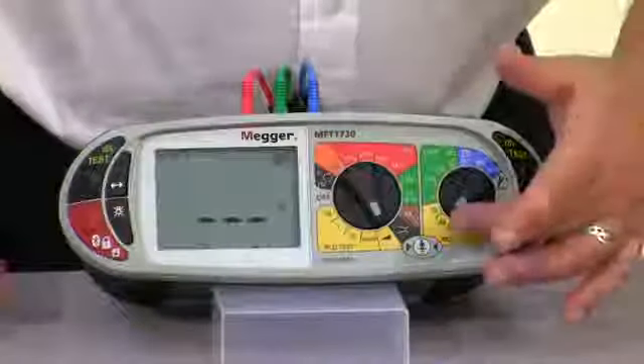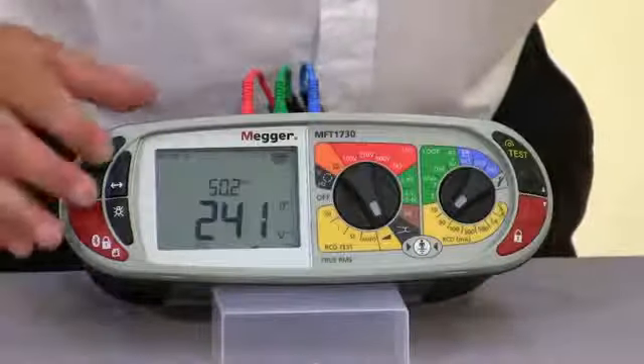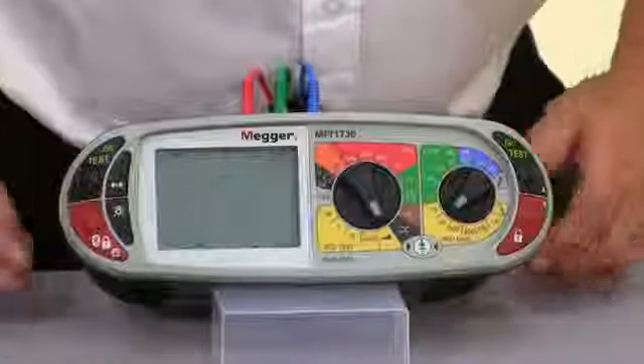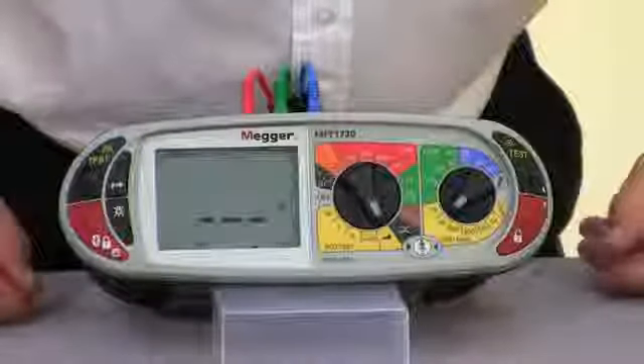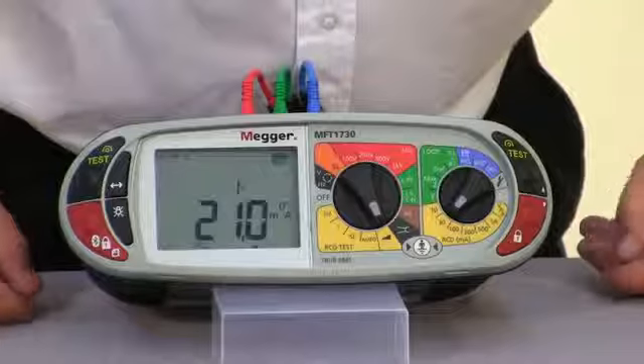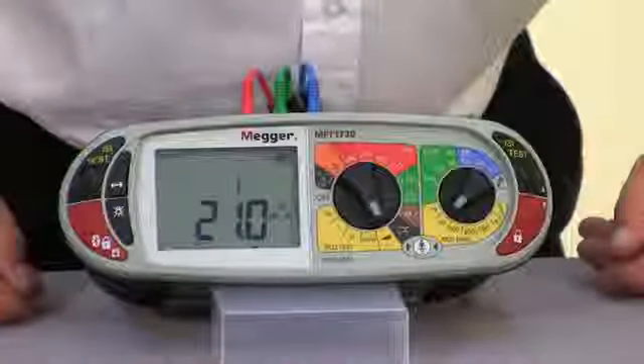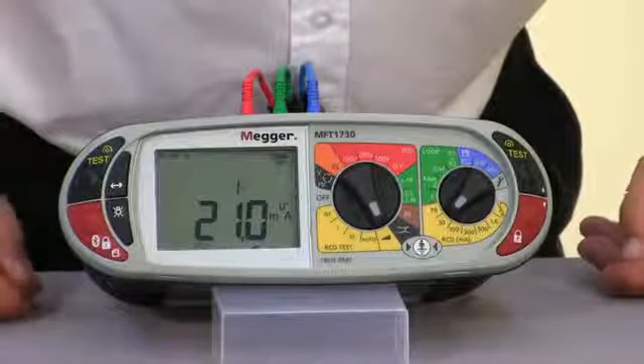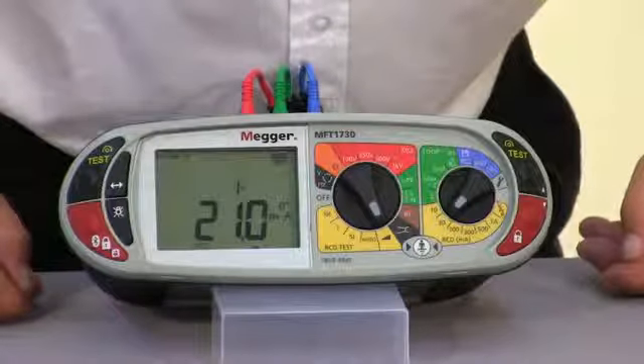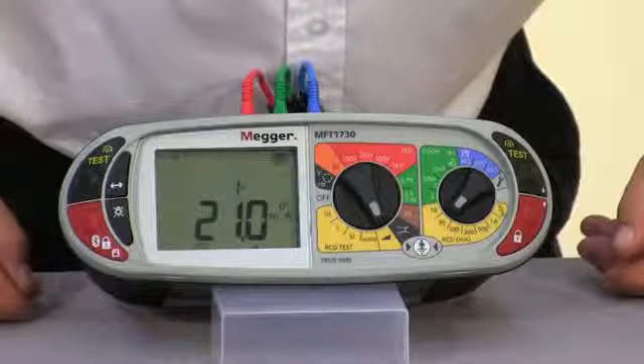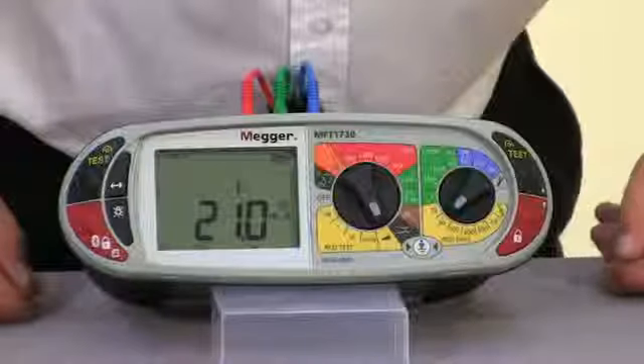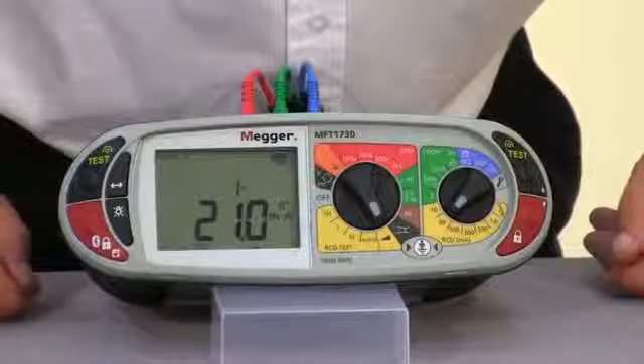The ramp test, again, with a standard 30 milliamp. We initiate the test. It will actually start at half the rated current of the RCD, and by ramping it up slowly indicate at exactly what value that RCD is operating. So in this instance we can see that the RCD actually tripped at 21 milliamps.